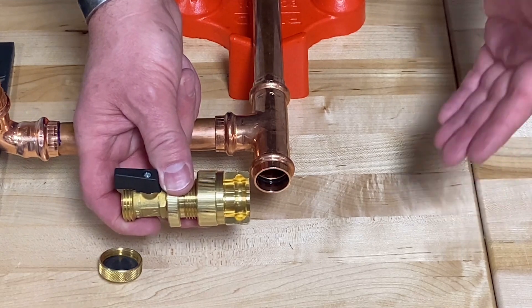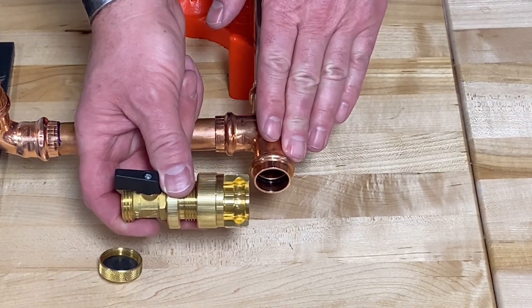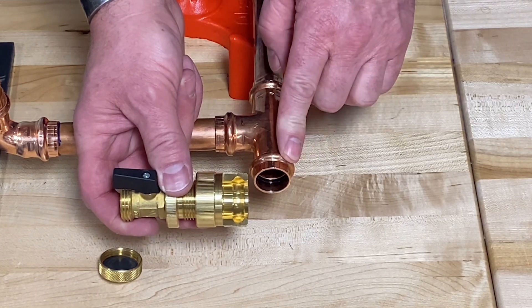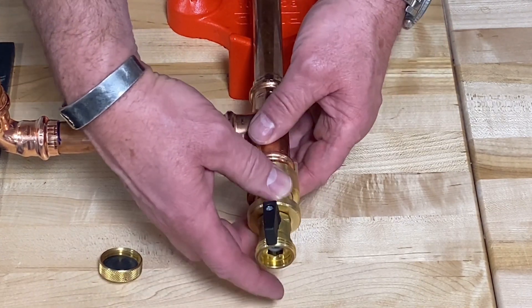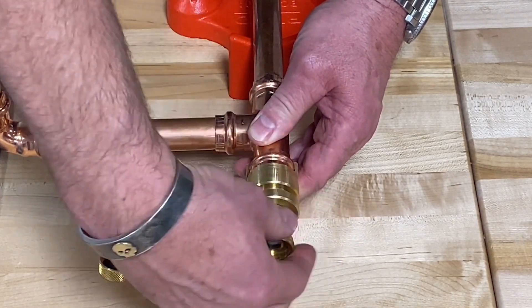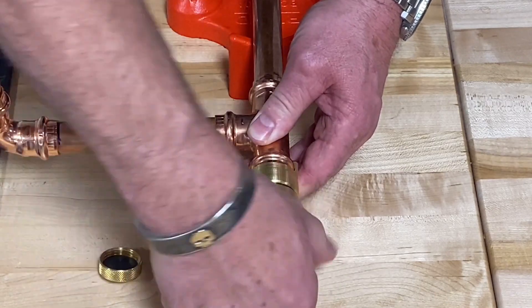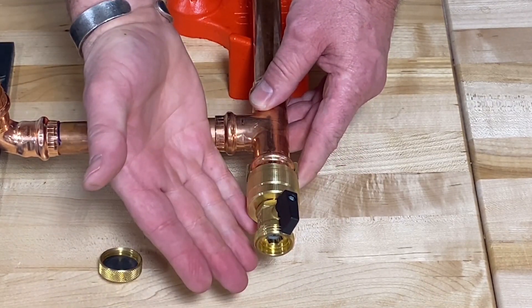The Viega ProPress Test Plug is an easy way to make a final commissioning test on your ProPress system at an unpressed hub of a ProPress fitting. You simply install the test plug onto the fitting, tighten down the collar until it inserts fully into the fitting, and then put your test on at the included hose bib.